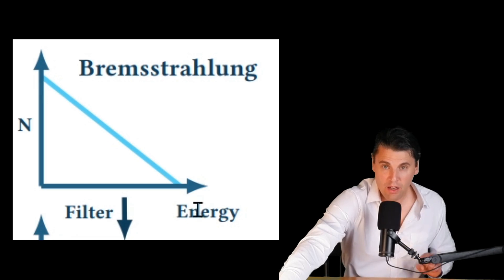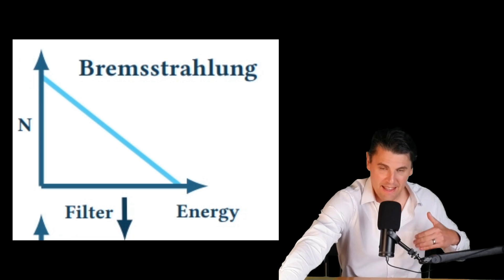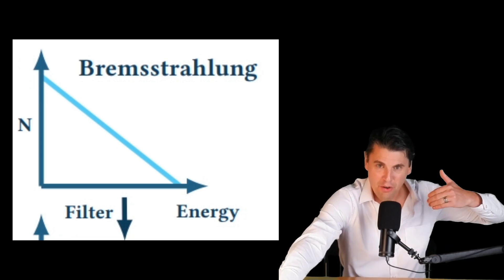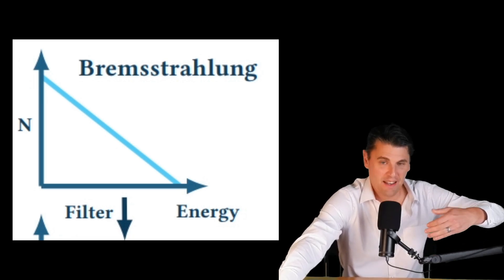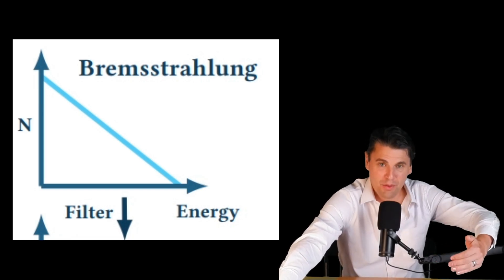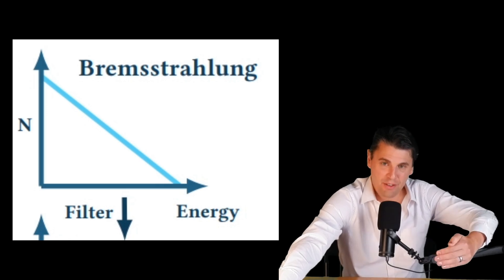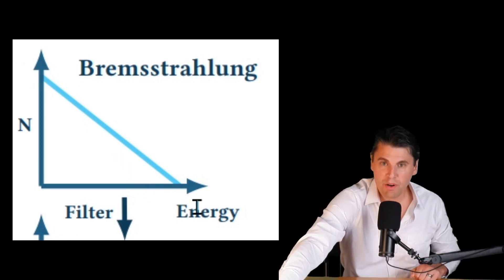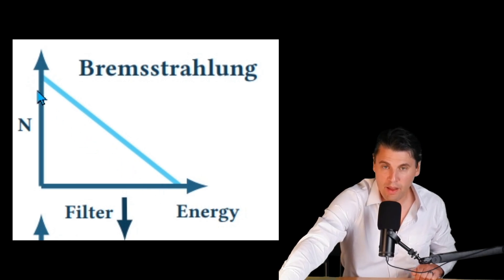Bremsstrahlung, as we've talked about, makes a nice continuous distribution. If you had just a perfect bremsstrahlung distribution, and the x-rays actually were just generated inside the anode, and they didn't have to leave the anode and pass through the tube and pass through additional filters, you would have something that looks like this, where you have more x-rays at the lower energy and then fewer at the higher energies.